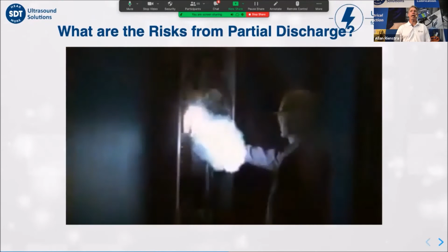But you know, there's tons and tons of information on the web about the dangers of arc flash and arc blast. And if you haven't read about them, then you need to be aware of them and the safety precautions that need to be in place for all of the inspections you do. One of the things I love about ultrasound is that we're always on the safe side of the fence. Notice in all these photos that I'm showing you right now that the inspector is in high voltage situations on the safe side of the fence, a safe distance away. Ultrasound detects defects which, when left to deteriorate, could lead to an arc flash event. And this doesn't suggest that ultrasound removes the need for personal protective equipment and other safety measures. I've yet to meet an arc flash suit which can detect an arc flash at its inception. But if you're wearing an arc flash suit as your last line of defense, ultrasound should be your first line of defense.